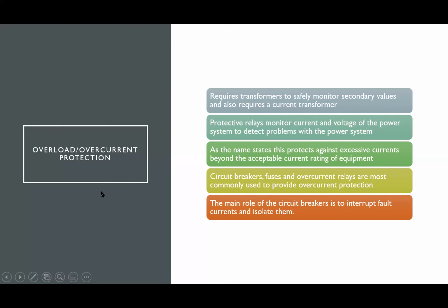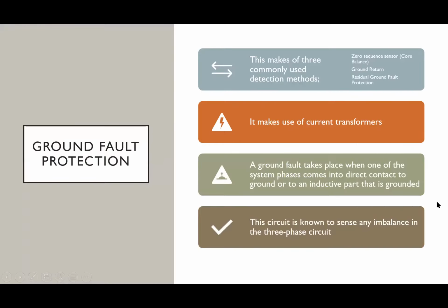And here we have the overload or overcurrent protection. This requires transformers to safely monitor secondary values and also requires a current transformer. Protective relays monitor current and voltage of the power system to detect problems with the power. As the name states, this protects against excessive currents beyond the acceptable current rating of equipment. Circuit breakers, fuses, and overcurrent relays are most commonly used to provide overcurrent protection. The main role of the circuit breakers is to interrupt fault currents and isolate them. Here we have the ground fault protection. This makes use of three commonly used detection methods. It uses the zero sequence sensor, also known as the core balance, the ground return, and residual ground fault protection. It also makes use of current transformers.